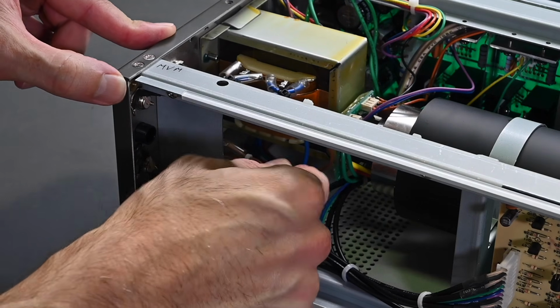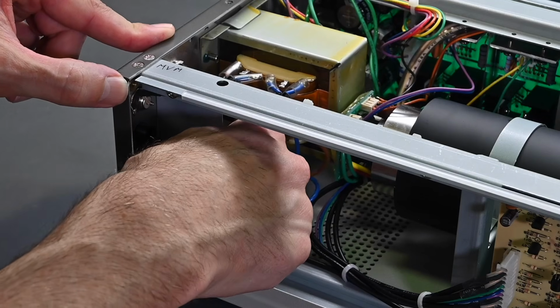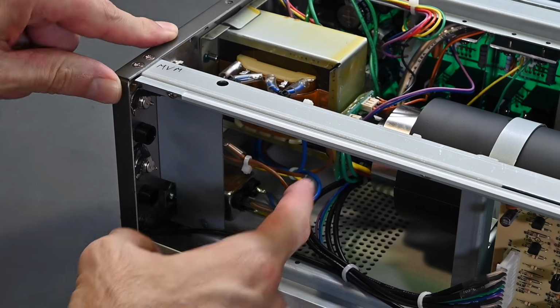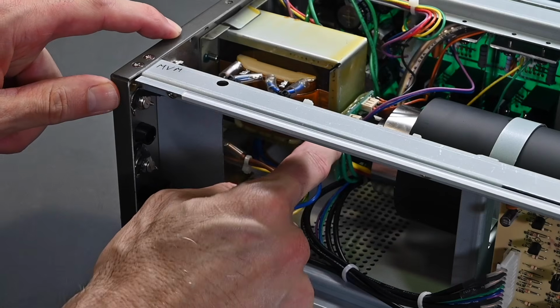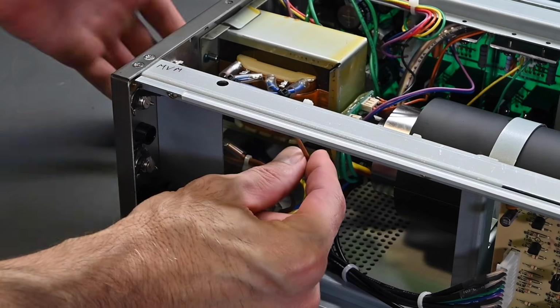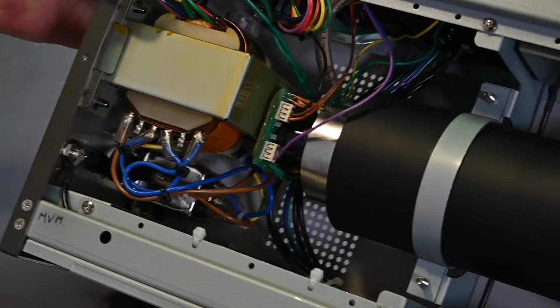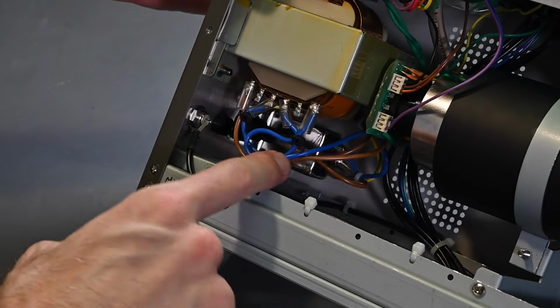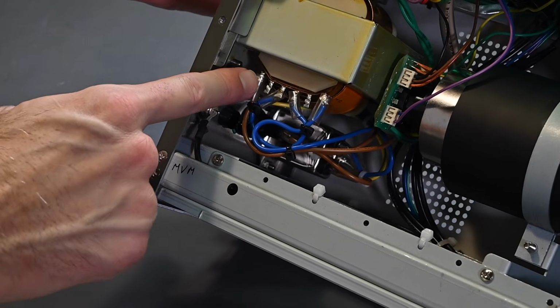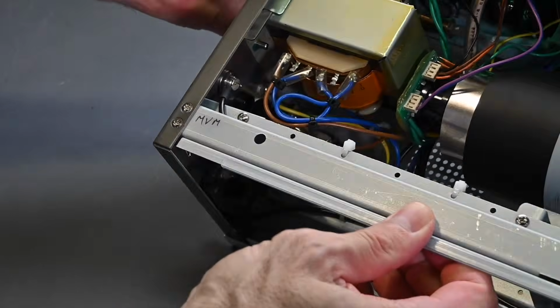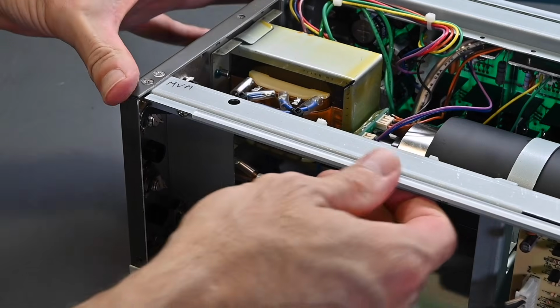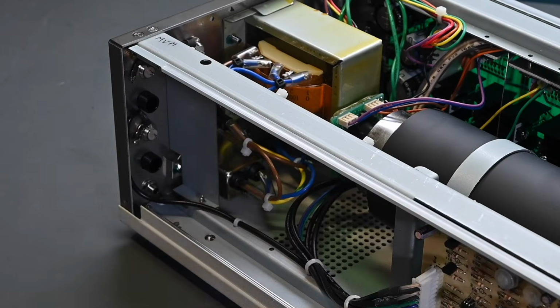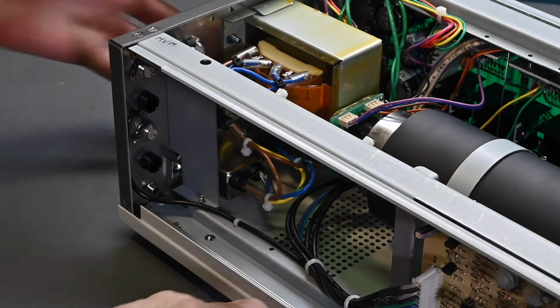Where is it going around here? Wraps over this way. Oh, it goes over to the switch. Okay, makes sense. So then this brown wire must be coming back from the switch. Okay, gotcha here. So that means the brown wire comes over to this tap, but we can see there's other taps on that transformer. And if I have a better view, yes, they are marked. Perfect. So that's going to make things a lot easier.